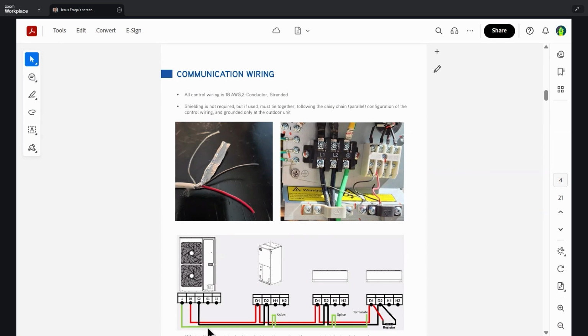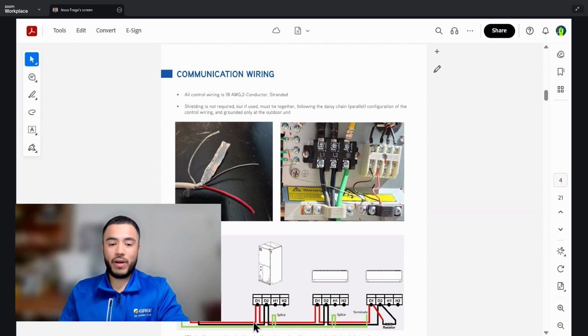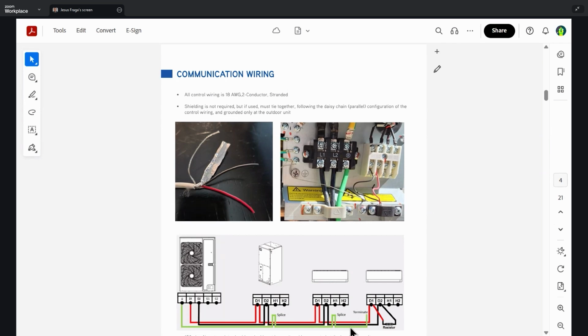And so you'll notice this grounded wire here. We have a splice in the first unit, splice in the second unit, and we're going to go ahead and terminate at the last unit. Now, this doesn't mean that we're going to land these wires in the middle of the communication method. So splicing, we know we're going to grab the ground going to the next unit and the ground coming from the next unit and pretty much splice it together here, splice it together here, and only terminate at the last point of contact in that data chain. And so this gives one path of interference, if there ever is any, in this communication data chain. So that means if there's some type of communication fault here or a ground, it'll travel its way out to the outdoor unit and terminate there and not in between the data chain communication.